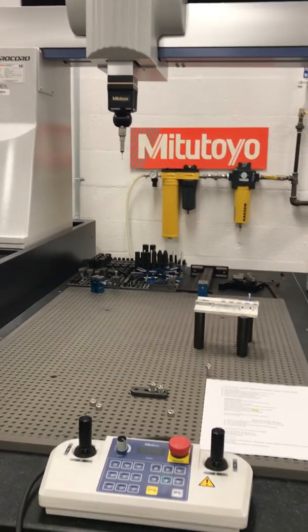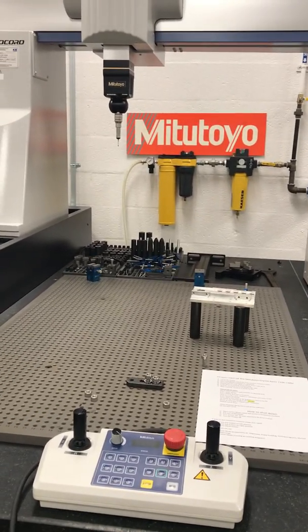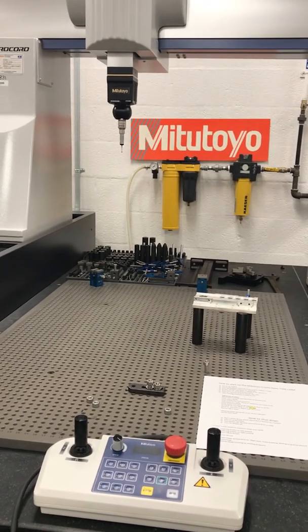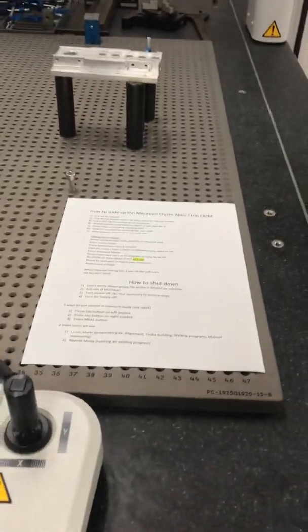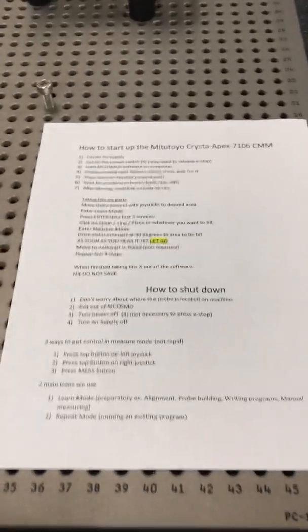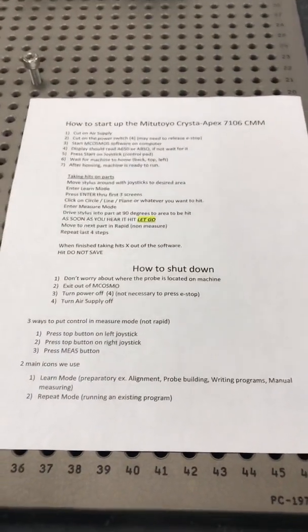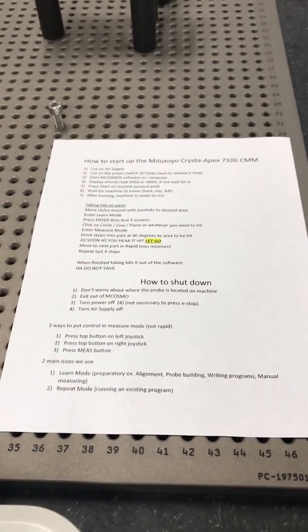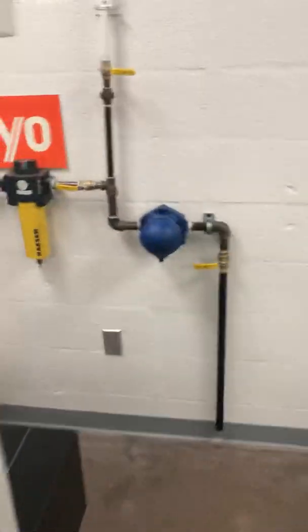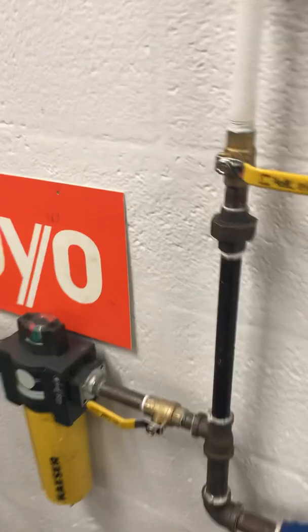Okay, we're going to talk about the startup and shutdown procedures of the Mitutoyo CMM. So on the module before, you'll have this sheet of paper, how to start up the Crysta-Apex 7106. So we will start. Number one, cut on air supply. The air supply is back here.